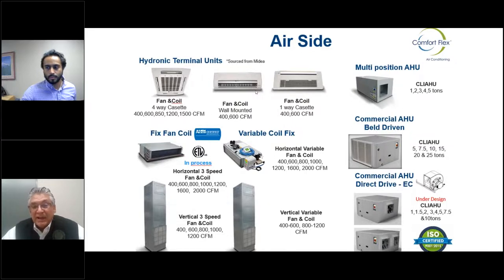applications. Now you can take that same type of design approach and bring it down to a 20 or 30 or 40 or 50 ton system, where now you have variable speed fan coils, variable speed compressors, variable speed condenser fans and variable speed pumps, and use pressure independent valves in each one of those fan coils. Now you have a real variable speed, variable water flow approach. Great for small tonnage, even larger jobs where you want a more systems approach to fan coils, chillers, and everything else combined.